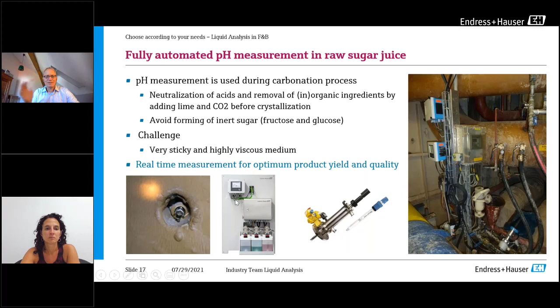That is a picture from inside the vessel. You can see the whole wall is covered with molasses, but the sensor is free. The reason is that they use a fully automated system. Regularly they remove the sensor and clean it with water. That is why the sensor is still working and not clogged with molasses, so it can be used during the whole season. So those were a few examples of the different pH measurements.